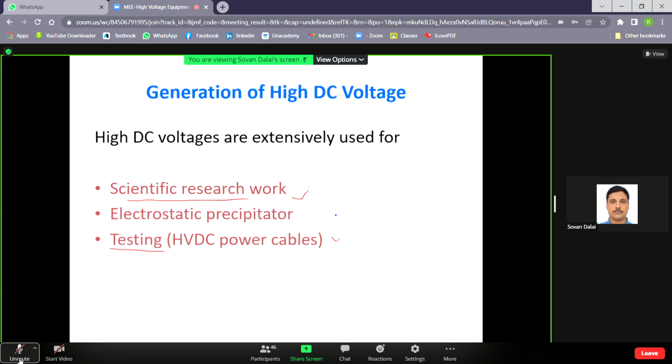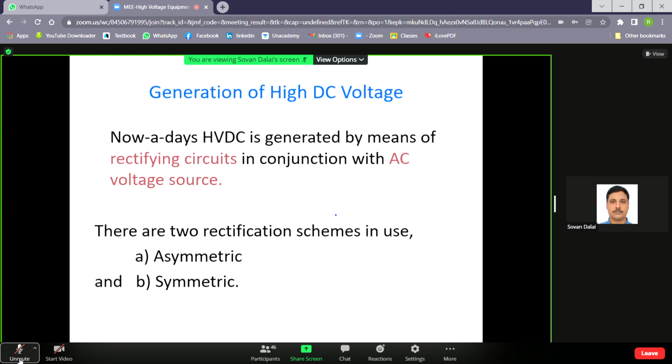But mind that for this rectifier, the correct one, you have to use the diode, and that diode may be made of say silicon, that diode may be made of selenium, or that may be a different one. But mind that this diode should operate at very high voltage, because the output voltage level for testing purposes is in the range of say a few hundred kilovolts. Okay, and the most common circuit for HVDC generation.